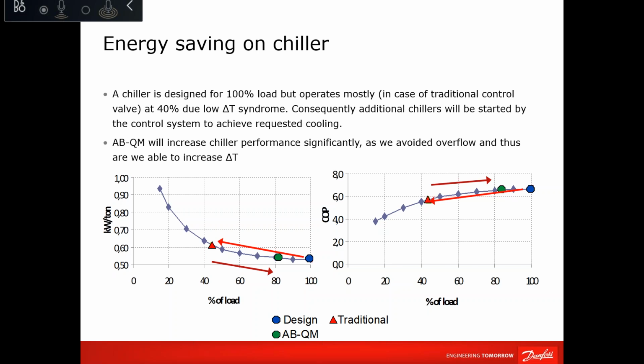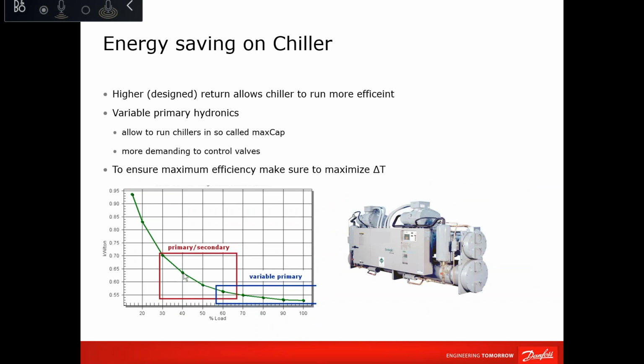So it's simple. The compressor is designed to compress refrigerant from 12 to 40, but because of the overflow in the system, this 12 is dropped to 9. Then the compressor will need more energy to heat up or to compress 9 to 40. So that is from where this saving would come.